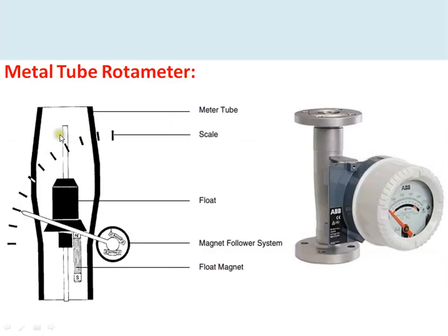Metal tube rotameters are used where transparent glass cannot be used — such as high-pressure applications or where the fluid is incompatible with glass. In a metal tube rotameter, the float moves on a guided pin and has a magnet attached to it. Movement of the float causes a needle to change position, providing direct local indication of the flow rate to the operator. Transmitters are also available so that, in addition to local indication, the flow data is transmitted to a PLC or DCS in the form of a 4–20 mA signal.